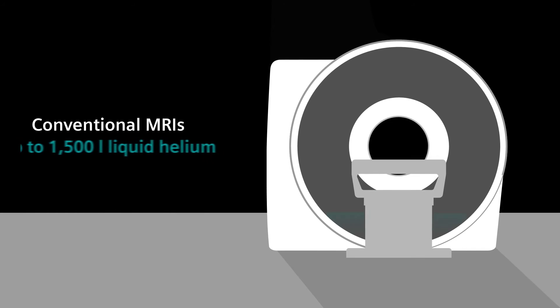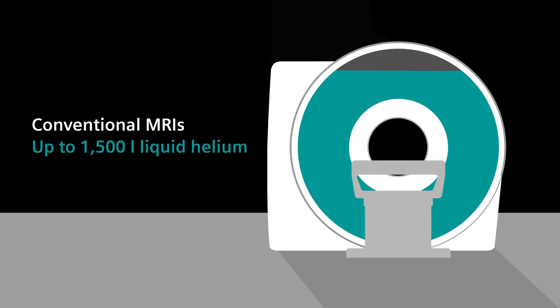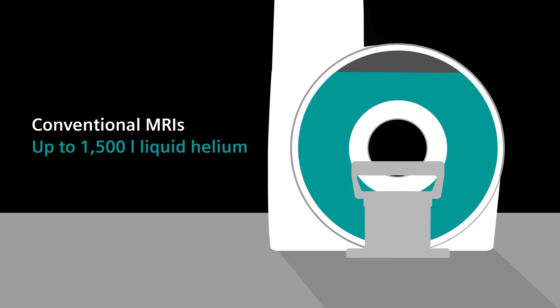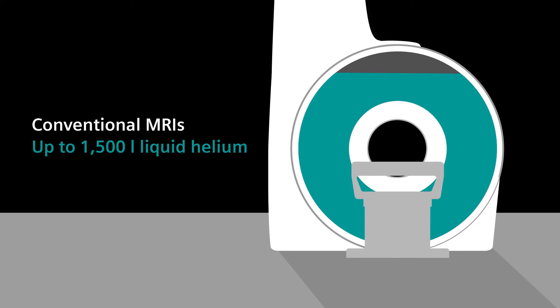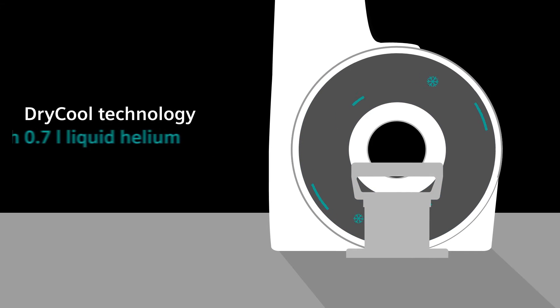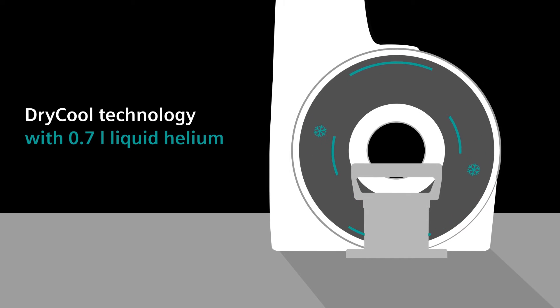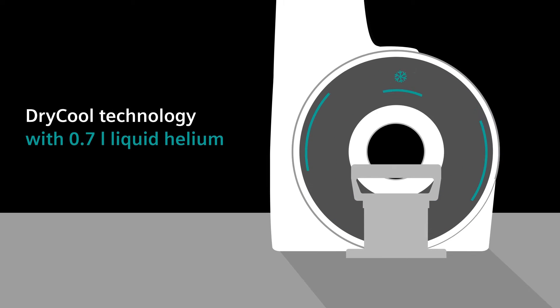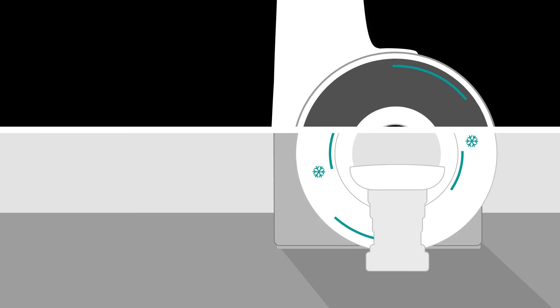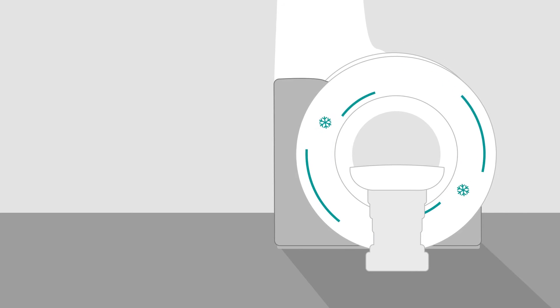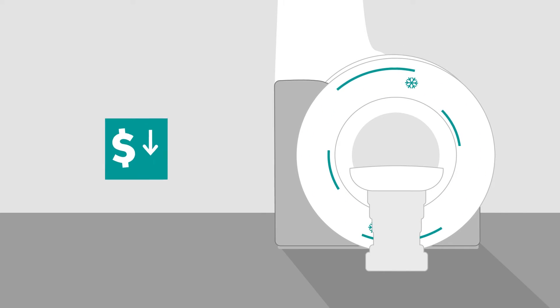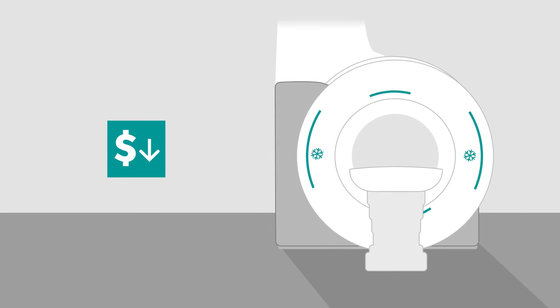Conventional MRIs require up to 1,500 liters of liquid helium and the costly installation of a quench pipe. DryCool technology has a sealed for life magnet design that operates with only 0.7 liters of liquid helium. This removes the barrier of helium dependency and the costly and complex quench pipe installation.